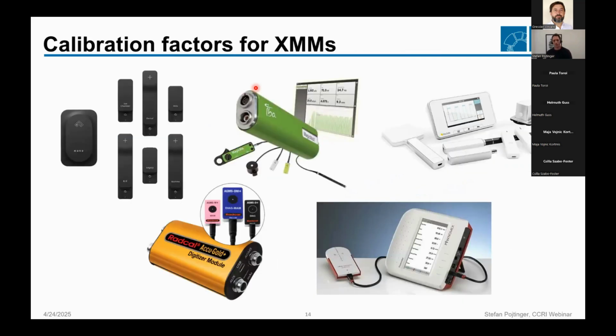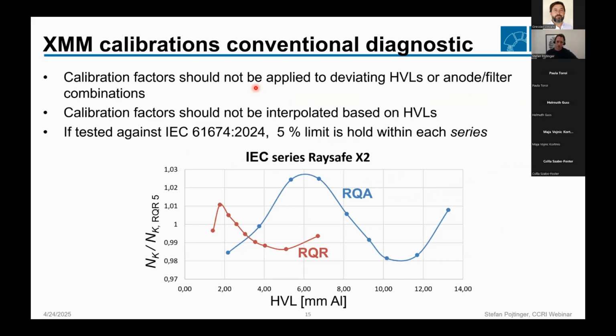Now, if we talk about XMMs, the situation is a little bit different. That's why I stressed it out for the ionization chamber so much. The energy dependence of the response of an XMM can be much larger than what we see for the very good ionization chambers. For example, here you can see calibration factors determined for Raysafe X2 XMMs. And here the calibration over RQR, where we have seen variations of less than 1% for the ionization chamber. And here for the XMM, you can see it's already 2%.